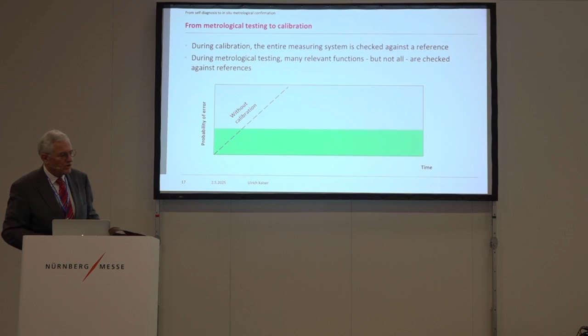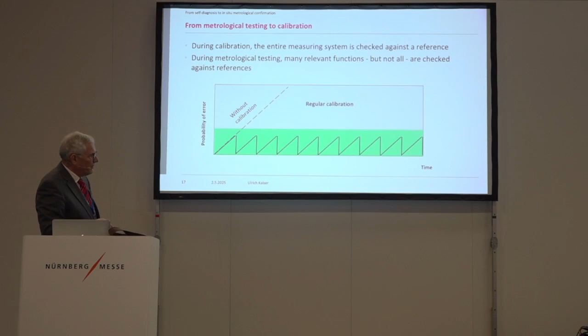And this is a way, when you have a process sensor and don't do anything, you have a certain probability of error, which increases with time. You say, I do a calibration, and then I do nothing. And the probability that your measurement value went out of specification gets higher and higher and higher. This is the idea behind it. And in order to keep it within operation, you do calibration or adjustments. You do a calibration, and then it starts again. And you do a calibration, and then it starts again, and so on. Typically these time distances are half a year, 3 months, 1 year.